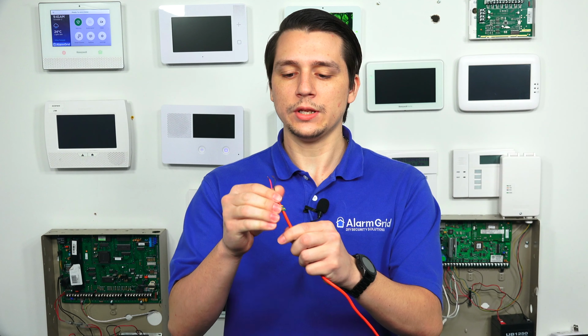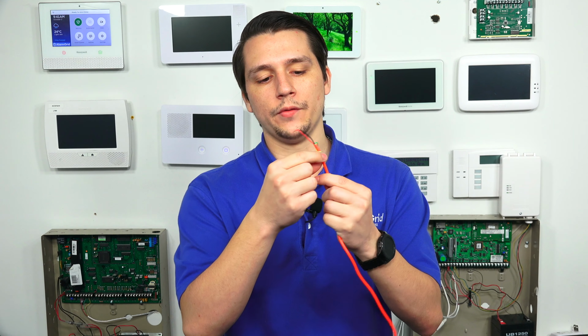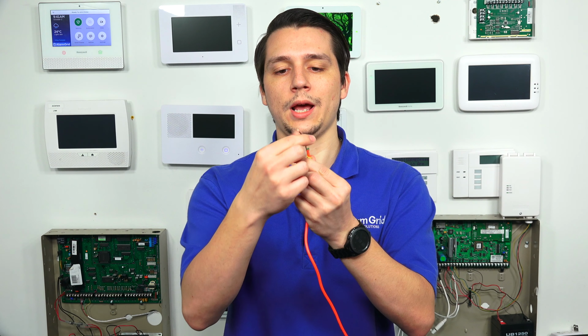This is an 18 gauge cable right here. This is actually 18 by 4 gauge cable. You see you have the yellow and green wrapping around it, but if you got 18 by 2 gauge cable, you're just going to have the positive and negative. Essentially, you're just going to be using the positive and negative to run power to the system. So the different gauge cables that we recommend are 18 by 2, 20 by 2, 22 by 2, or 16 by 2. Yeah, 16 by 2 can also be used as well. It's not always recommended for other types of systems, but for the 2GIG system, you can do that.